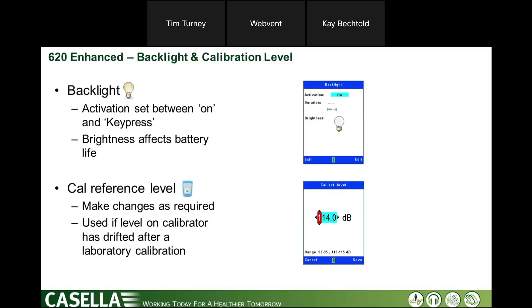You can adjust the calibration reference level in the settings. For example, if after a couple of years you send your calibrator for calibration and its level is now 114.1 dB, you can adjust that in the settings so when you put the calibrator on next time it will be at the correct calibration level.